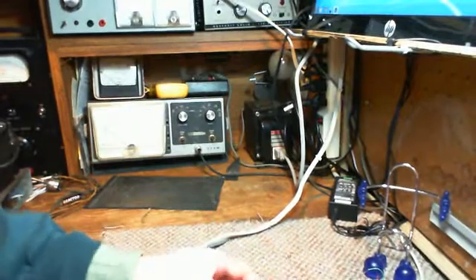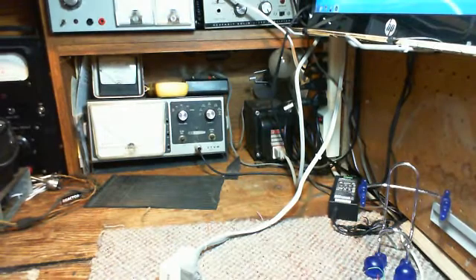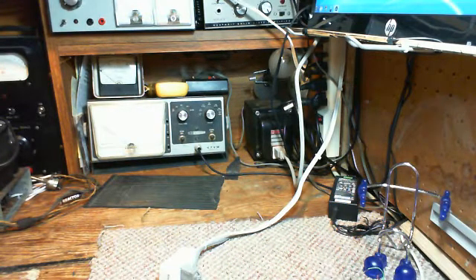Hi everybody. I'm going to take just a few minutes and try to convince myself that my isolation transformer right here really is isolating — that it really does have an isolated output from the input, and that there's not an internal ground connection between the power company ground or my neutral, and the output side of it. It's got a three-prong plug on the output side, so if that's a proper isolation transformer, I'm not sure what the third prong would connect to.